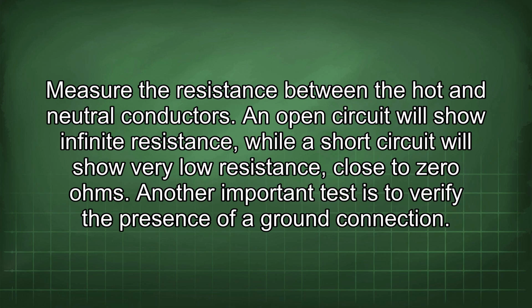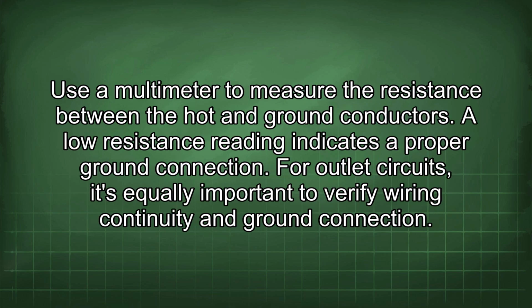Another important test is to verify the presence of a ground connection. Use a multimeter to measure the resistance between the hot and ground conductors. A low resistance reading indicates a proper ground connection. For outlet circuits, it's equally important to verify wiring continuity and ground connection.